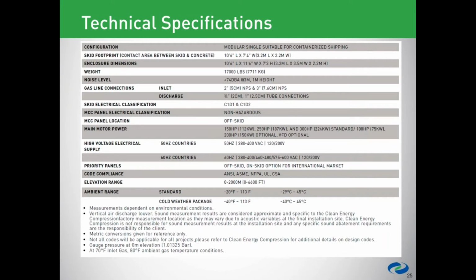So it says here, what are the consequences of not having the package? I'm assuming that means not having the enclosure. Sure. So there's a number of things. The airflow is slightly degraded because we're not funneling it as well as we like to with the enclosure. For example, the inlet louvers on the compressor package are specifically designed to direct the airflow over the compressor block, which keeps the compressor block cooler, reducing interstage temperatures and the oil temperature. Again, the noise level is a big one that increases without having the enclosure.